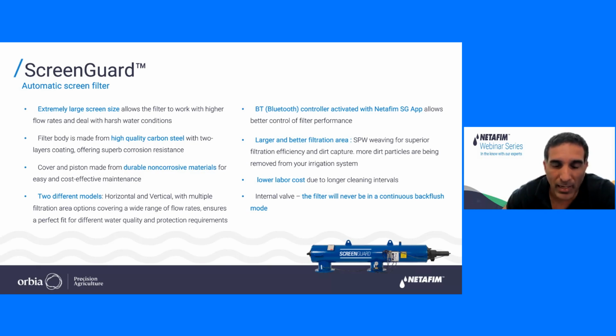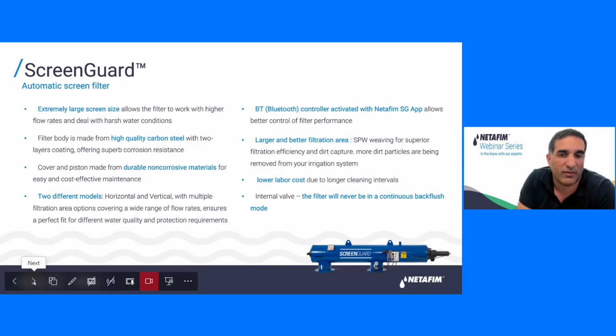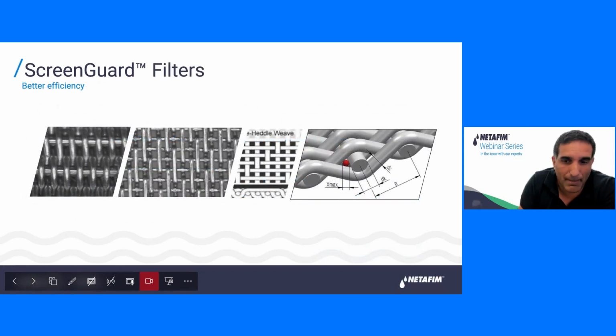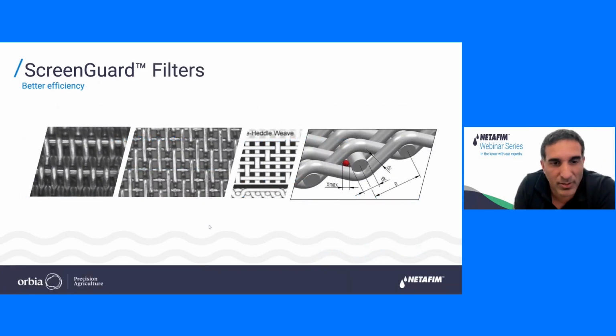Another feature that is very unique here is that we have an internal valve. That means that the filter will never go into continuous backflush, as we know that screen filters used to do. Once there is a failure and the backflush doesn't work properly, the filter can go into continuous backflush. In this case, the internal valve will go into a single backflush, and then it will stop there. There wouldn't be a chain of backflashes as in other filters that you know.